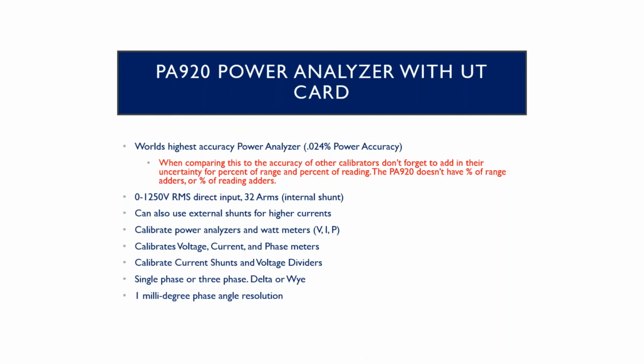The other thing about the PA920: with one card, it can do single phase, but you can put 3 cards in there and it can do 3-phase delta or Y as well. One of the nice things about this is it's a digital system. We digitize the signals coming through and we measure the phase. The phase is calculated as opposed to measured because it's all a digital signal. And we measure phase with a millidegree phase angle resolution.